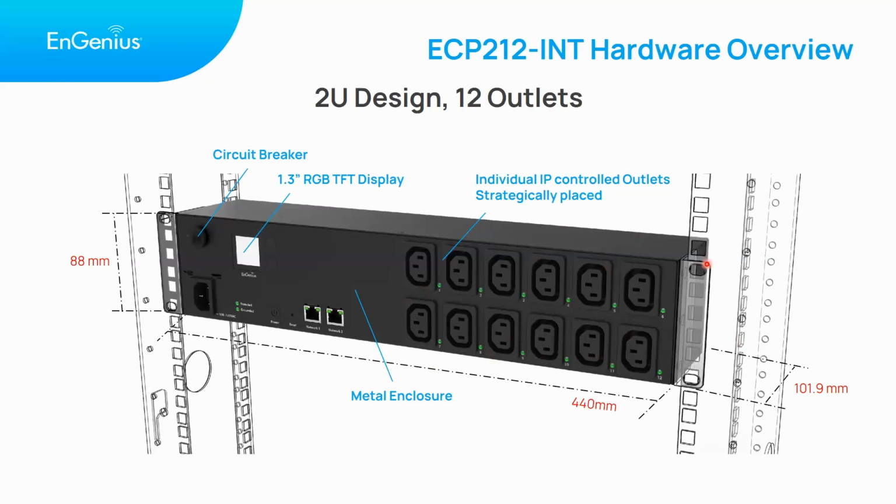What is the default IP address of the PDU? Because if we try to customize anything without adding it on the cloud portal. So the PDUs would have a default IP address. I don't have one in hand right now, unfortunately. But they would have a default IP address similar to what we have on our APs, switches, and gateways. Each of our product platforms has a different default IP. For example, APs are 192.168.1.1, switches are 192.168.0.239, and the gateway is 192.168.66.1, depending on your DHCP service. For the PDU, I believe they would carry their own unique starting IP as well. But by default, they would also be on DHCP. So if you plug it into a network switch, they would automatically grab an IP from your switch. But you would be able to access the PDU first in case you need to configure, let's say, your management VLAN, maybe a specific gateway or DNS service. That type of information you can configure beforehand before adding it on the cloud.